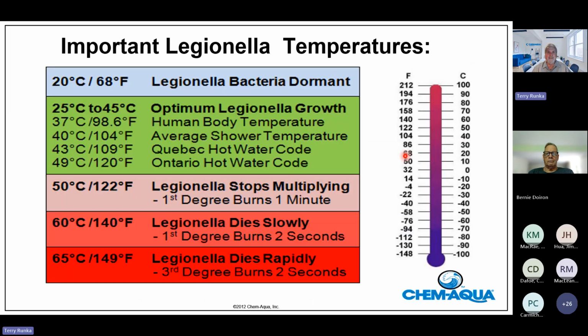Now, I never know where to put this slide, but it's important. Temperature is very, very important to a lot of bacteria, but especially to Legionella bacteria. Below 20 degrees C, Legionella bacteria is dormant. We used to think it was dead or wasn't alive. We now know it's dormant. Then when it warms up, it becomes viable again. From 20 to 50 degrees C, Legionella bacteria grows. Ideally, 25 to 45 degrees C is the optimum Legionella growth temperature. Well, what else happens in that optimal growth range? The human body temperature. That's why we're such good hosts for it. Nice, dark, wet lungs at the perfect temperature. The average shower temperature is right in that optimum growth.